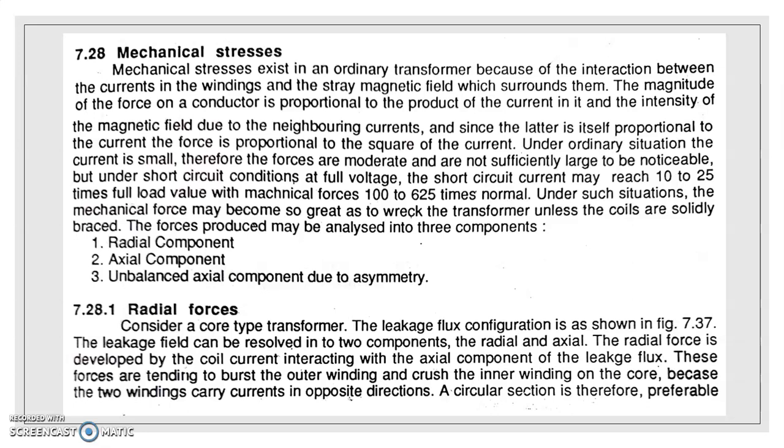on the transformer core, and the magnitude of that force depends on the product of the current and the intensity of the magnetic field produced by the neighboring currents. You can also observe that the force exerted on the core of the transformer is proportional to the square of the current. So under normal conditions the current is small, therefore the forces are moderate and not large enough to be noticed.